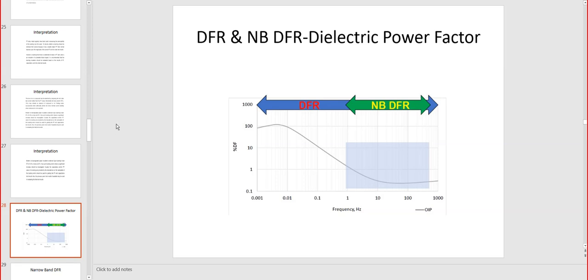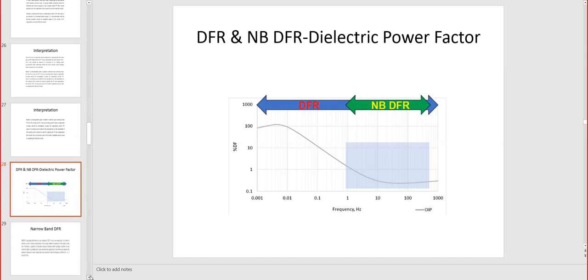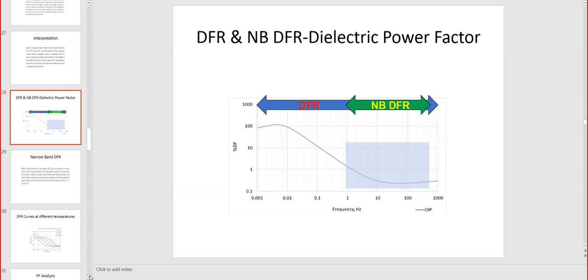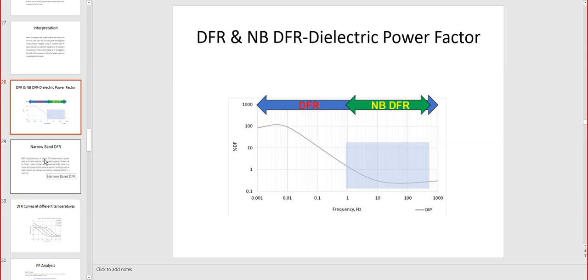So this is a dielectric frequency response, and you have two types. There is the narrow band, NB DFR, that only considers the test from 1 hertz to 1000 hertz, or even less than 1000. It's not going through the low frequency response that we have on a complete dielectric frequency response. And there are charts and recommendations from Doble, and we're going to see those recommendation values.